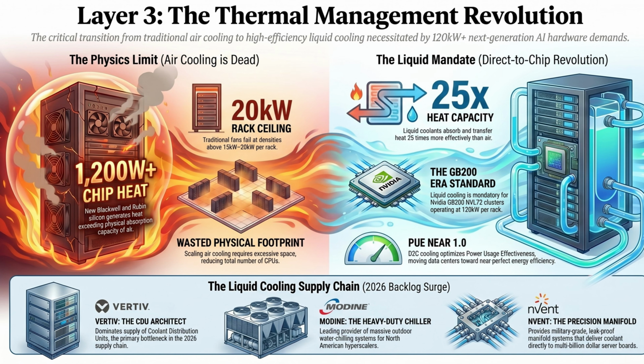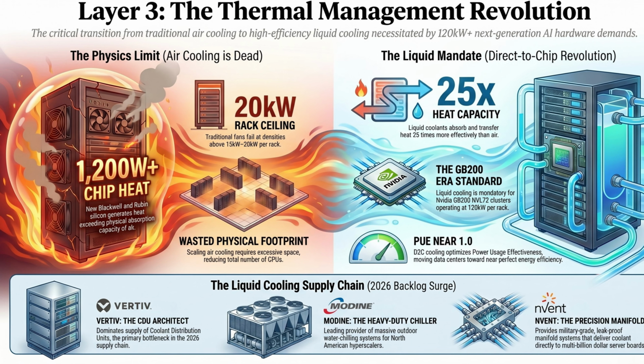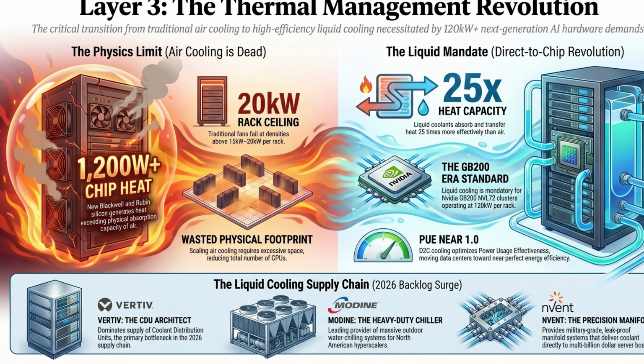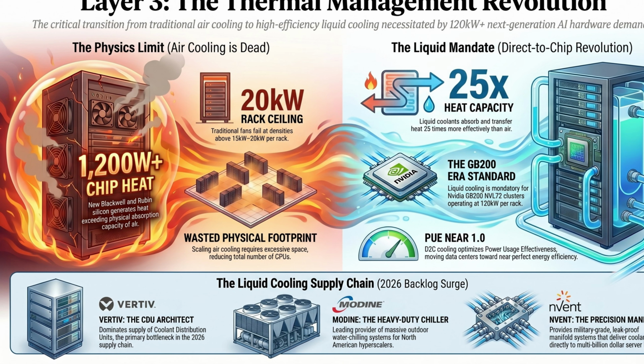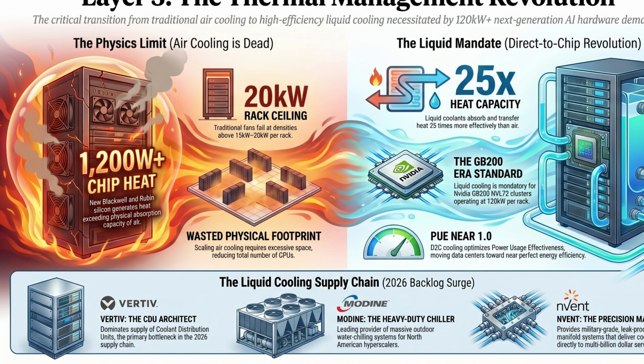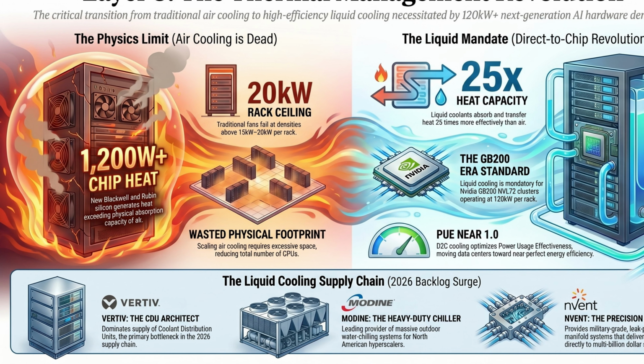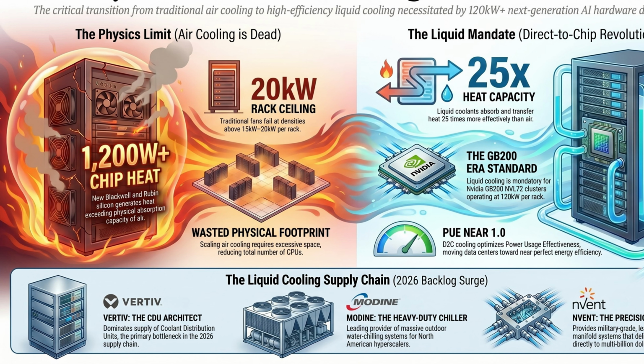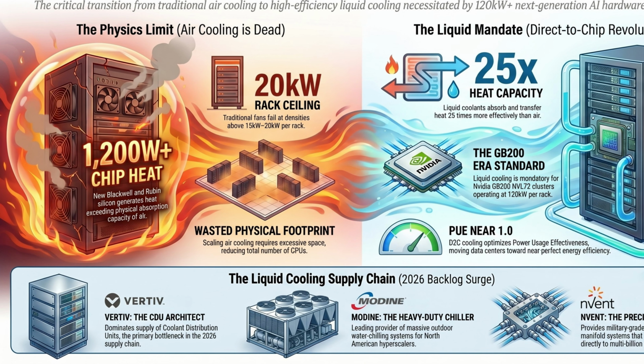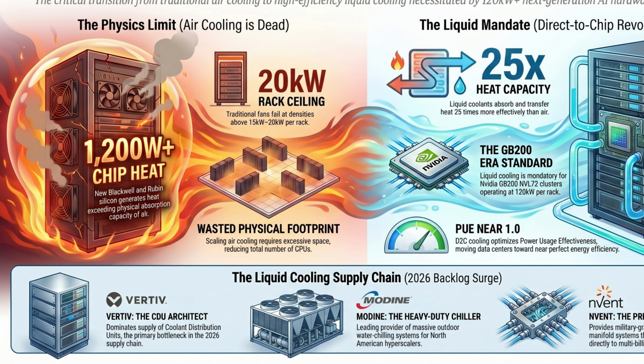Reaching the silicon level, traditional physics collapse. Next-generation Blackwell and Rubin chips generate brutal heat, exceeding 1,200 watts per chip. Traditional air cooling hits a hard ceiling at 20 kilowatts per rack. Trying to scale it results in a severely wasted physical footprint.